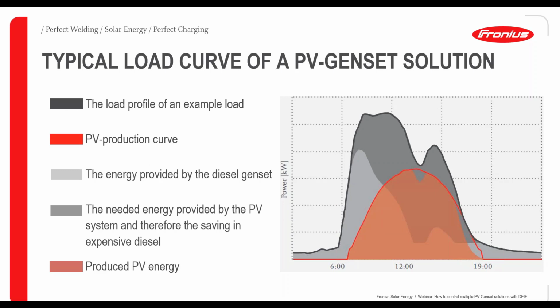Yeah, I quickly want to show you just a typical load curve of a PV genset solution. We can see here the gray line, the load profile of an example load. We have it over the whole day, and in the red line we have the PV production curve during the day. With the light gray area, we see the energy that is provided by the diesel genset, and we can see it's providing the whole base load for the system also during the night.